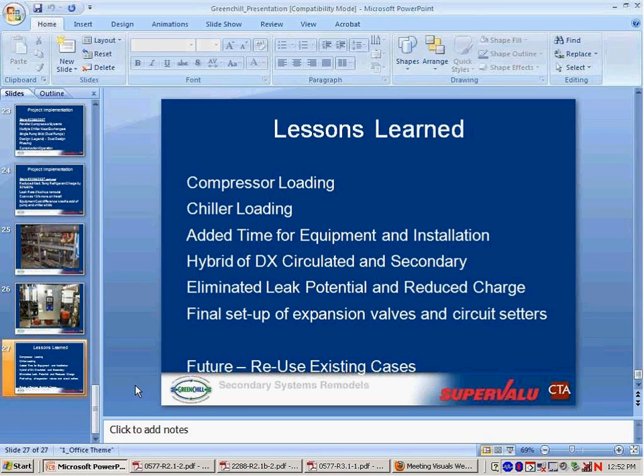As Ron pointed out earlier, when you add a pump skid, you're taking essentially the same compressor horsepower and reusing it, but you're adding a pump skid, so you'll have additional energy devoted to that. If you can reduce cycle counts because you've got a more stable load on the plate heat exchanger than you would on multiple evaporators and cases, that's certainly going to help your energy by reducing cycle counts and run times on rack compressors and whatnot.